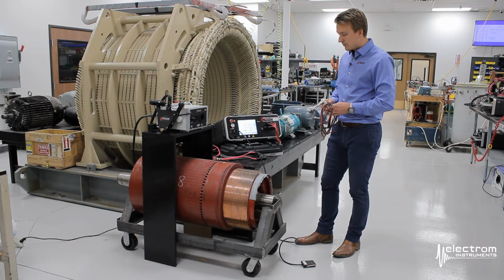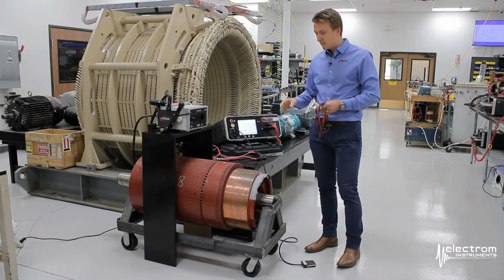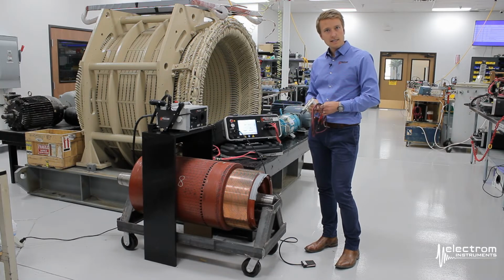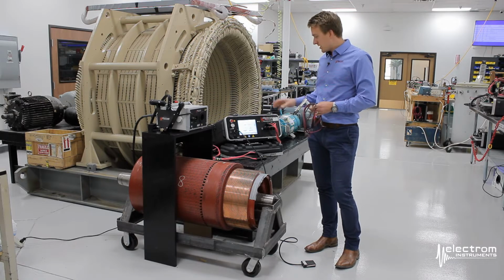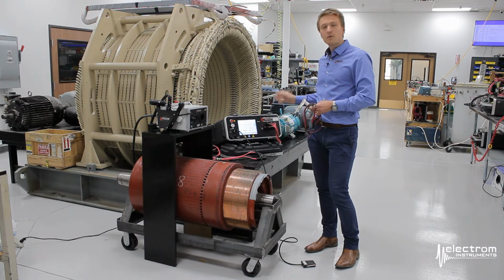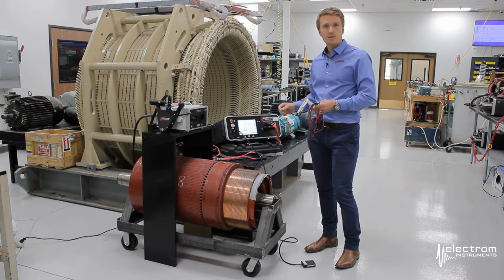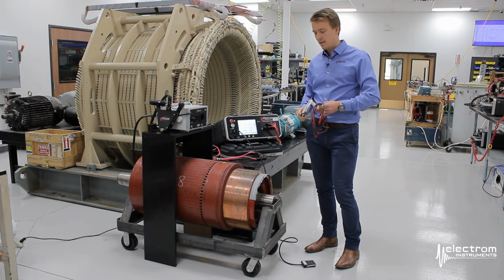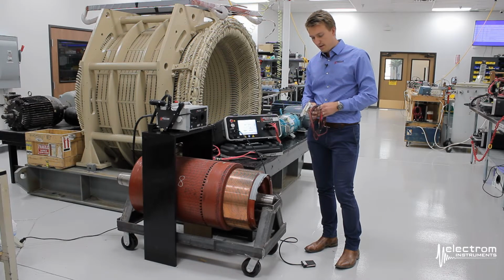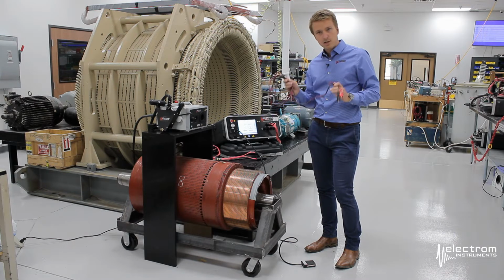So that means the voltage accuracy will not be as good as it is with the ABT. What you will see on the screen will, in most cases, be higher than what's actually applied on the armature. That's because there is some voltage drop across the test leads.